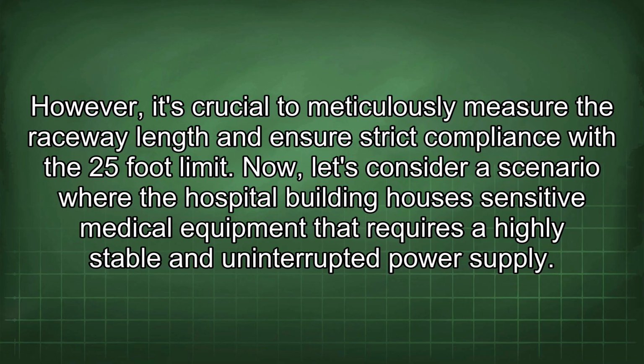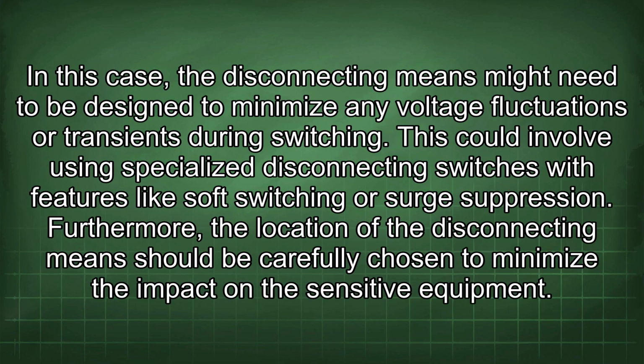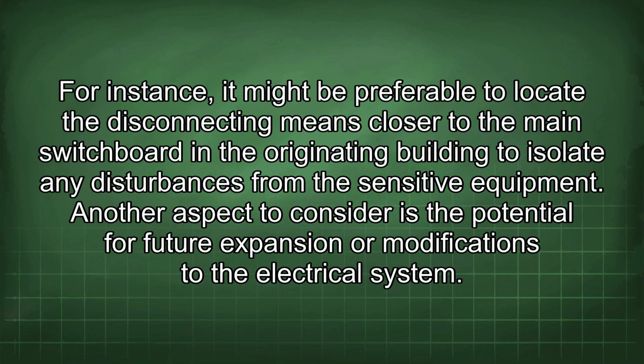Now let's consider a scenario where the hospital building houses sensitive medical equipment that requires a highly stable and uninterrupted power supply. In this case, the disconnecting means might need to be designed to minimize any voltage fluctuations or transients during switching. This could involve using specialized disconnecting switches with features like soft switching or surge suppression. Furthermore, the location of the disconnecting means should be carefully chosen to minimize the impact on the sensitive equipment. For instance, it might be preferable to locate the disconnecting means closer to the main switchboard in the originating building to isolate any disturbances from the sensitive equipment.